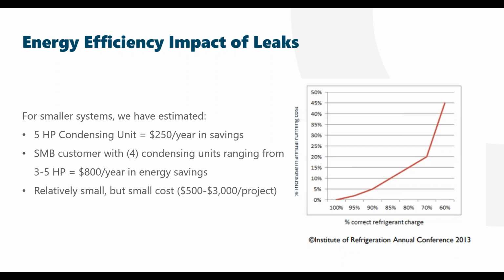For smaller systems that don't have a liquid receiver, which gives you a little extra buffer of refrigerant, leaks may be less impactful at a certain point on energy consumption. For these smaller systems, we've estimated savings and launched a program in Vermont to support small and medium customers with refrigerant leak repair. Here are some high-level energy savings estimates we've developed through a TRM. It's relatively small energy savings, but also a relatively small cost. Typically what we've seen for a comprehensive refrigerant leak audit and repair is $500 to $3,000 per project, ranging from a small convenience store to a large grocery store where a contractor is on site for 3 days. So these really can be cost effective from energy savings alone, but there are plenty more benefits. Next slide, please, Zoe.